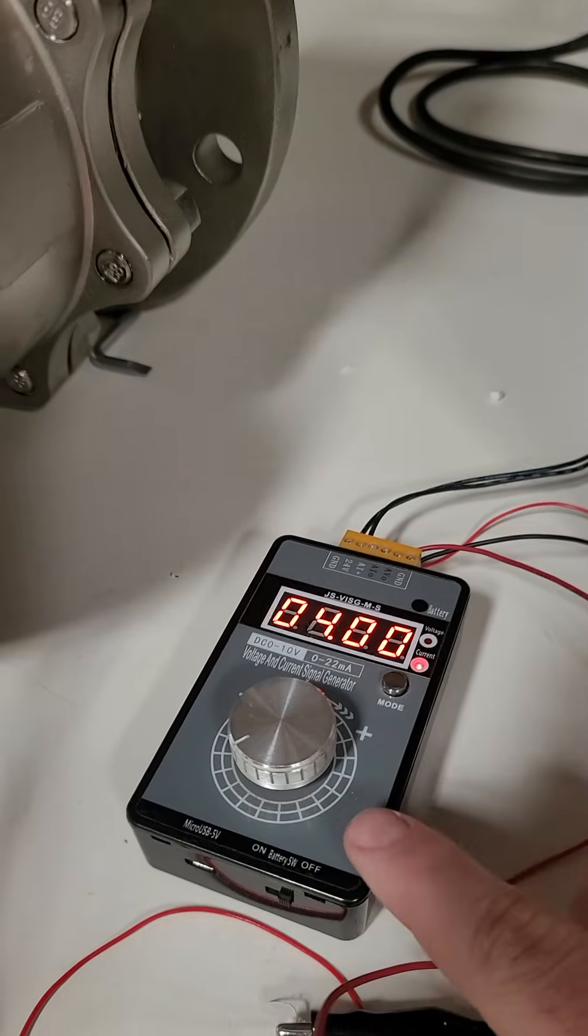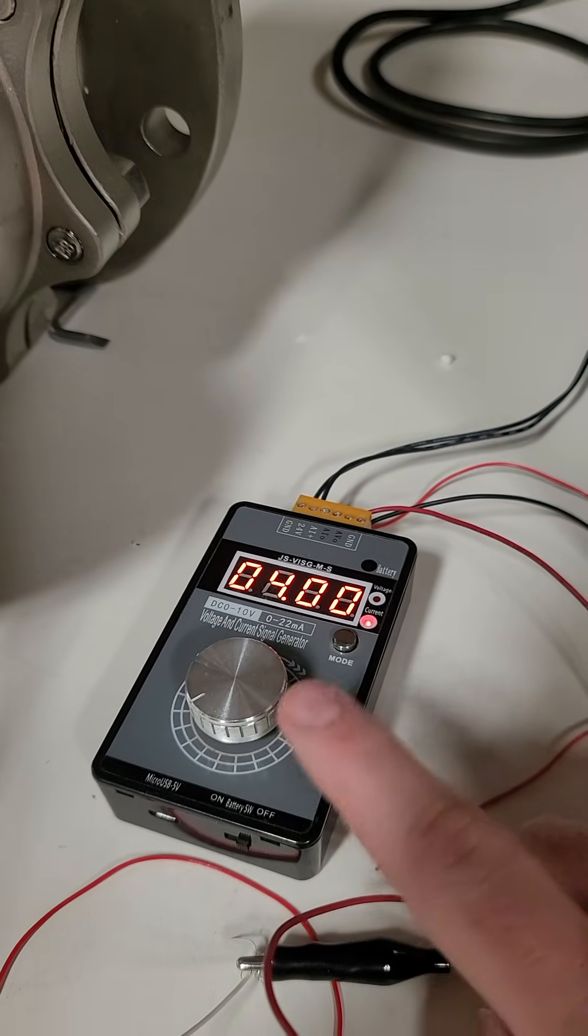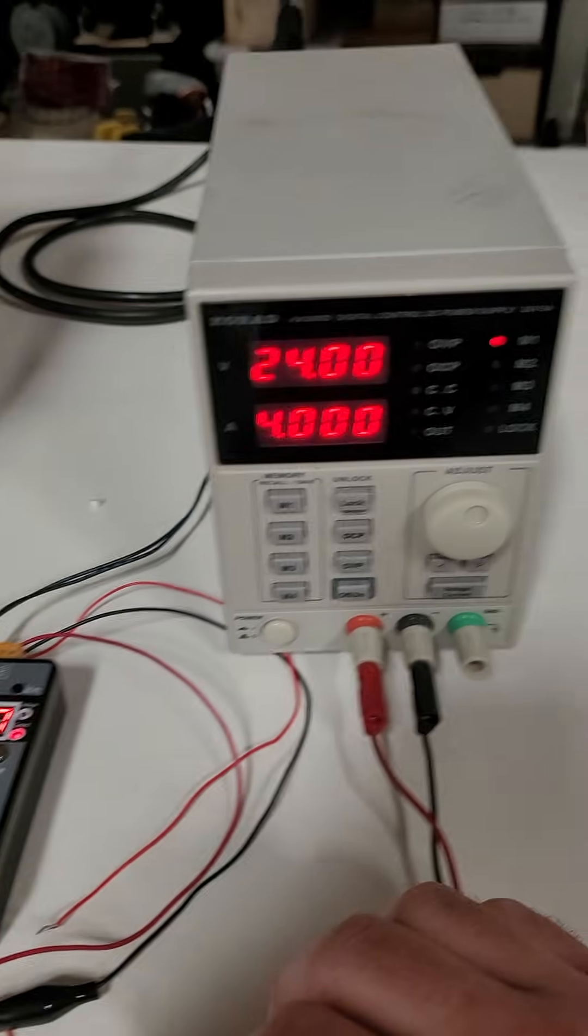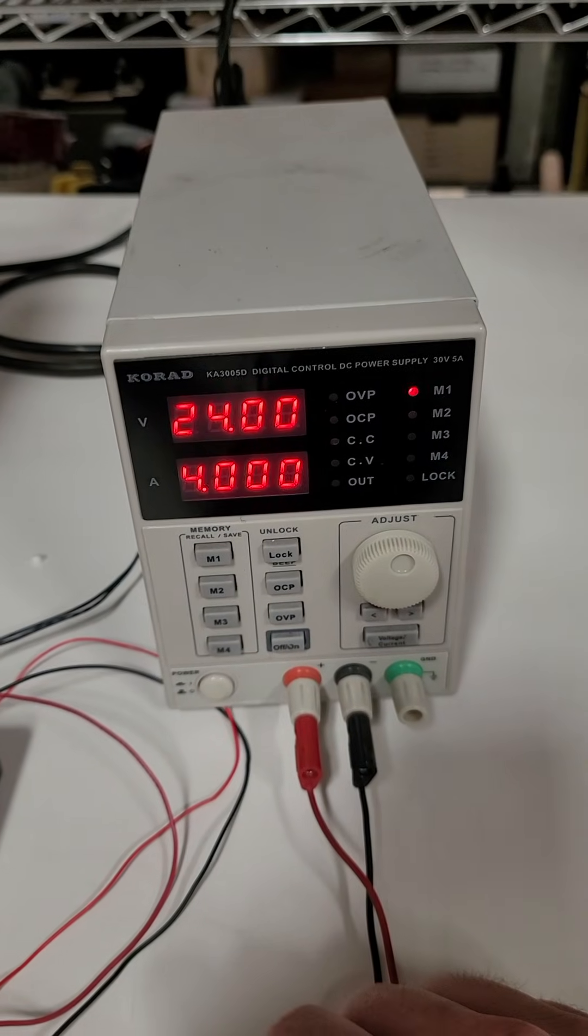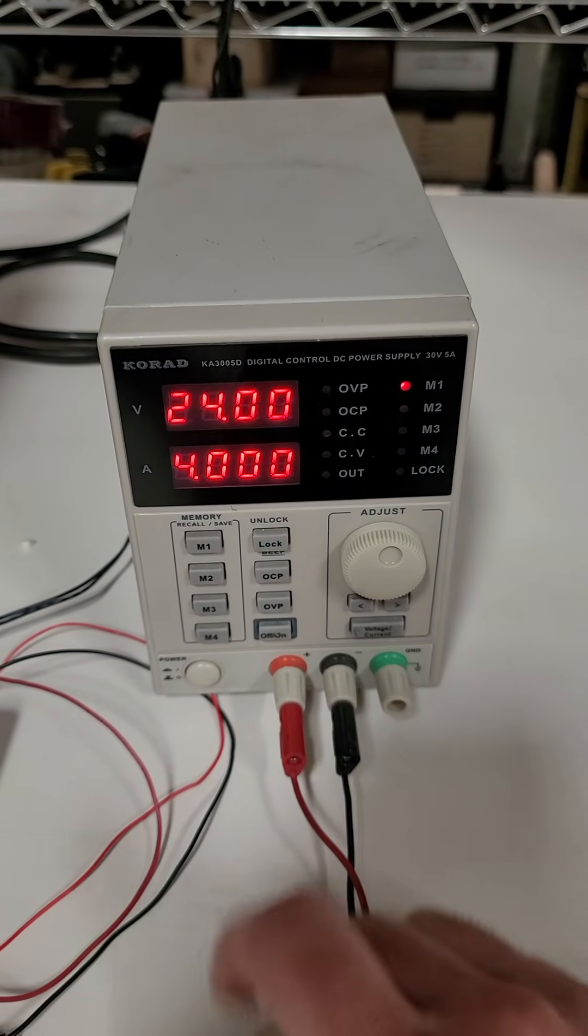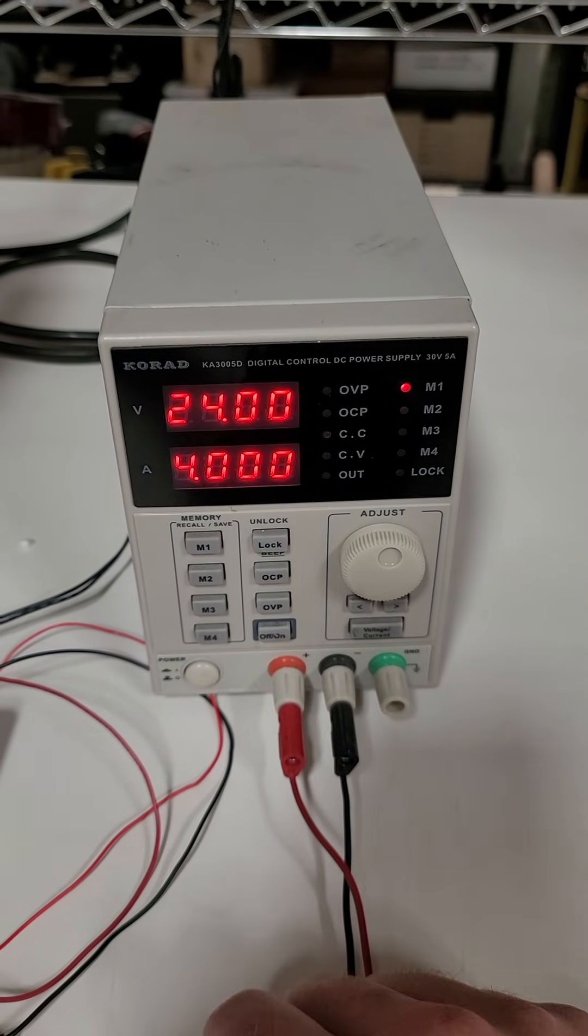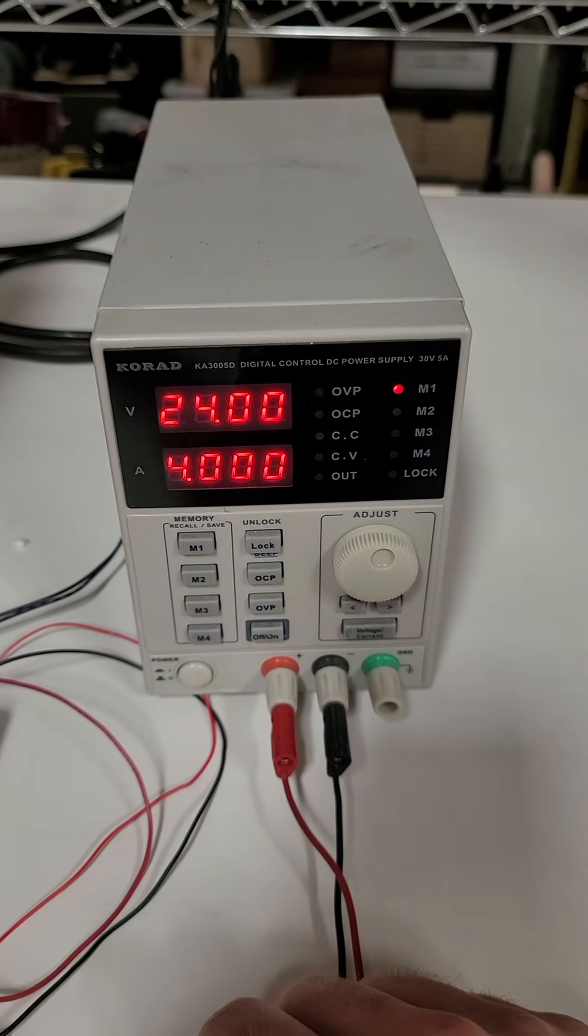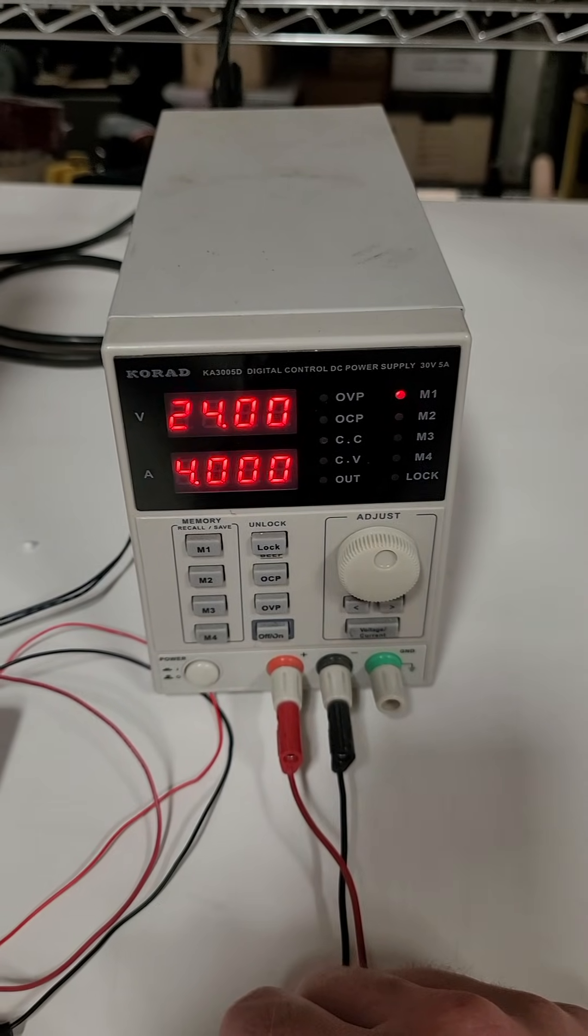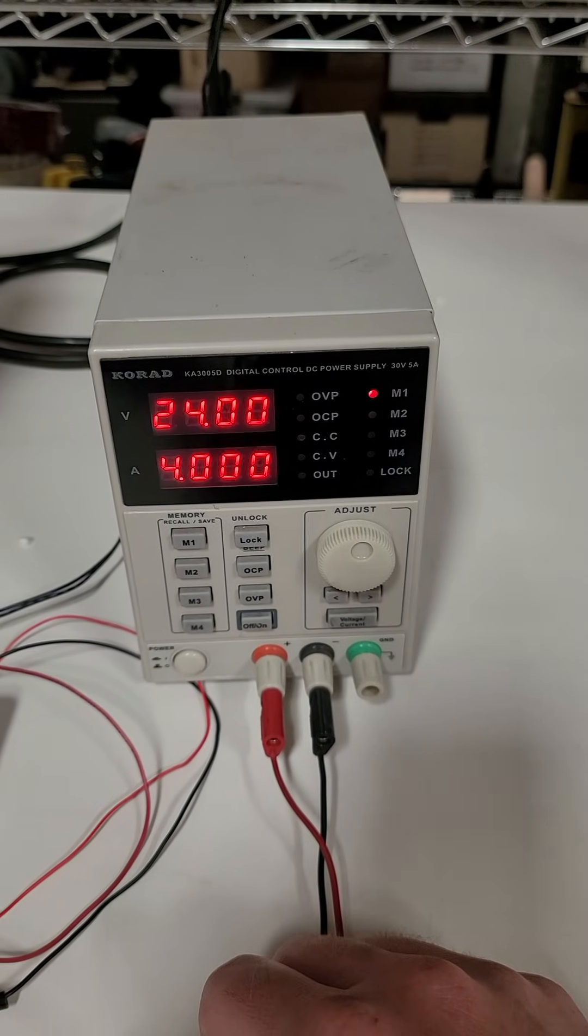We have it currently hooked up to a 4 to 20 simulator. For the power on these big control valves, we have 24 volts at 4 amps, so you need to have a pretty big power supply to control these.